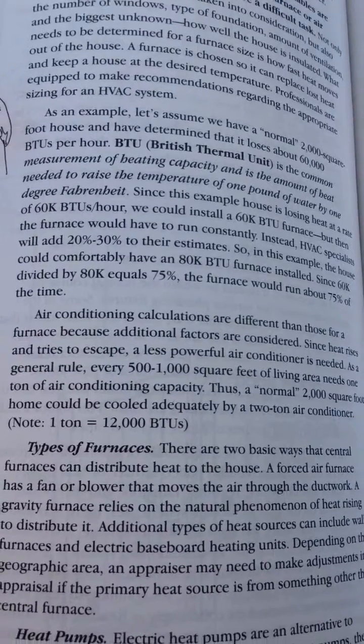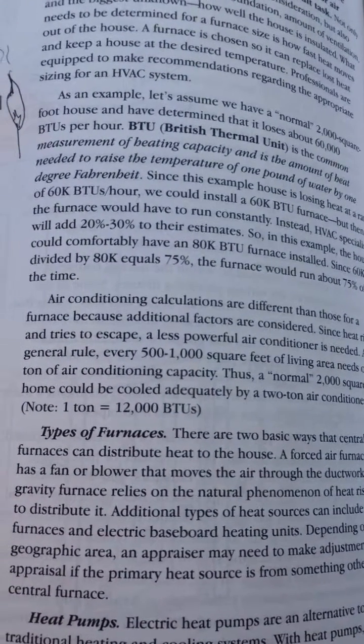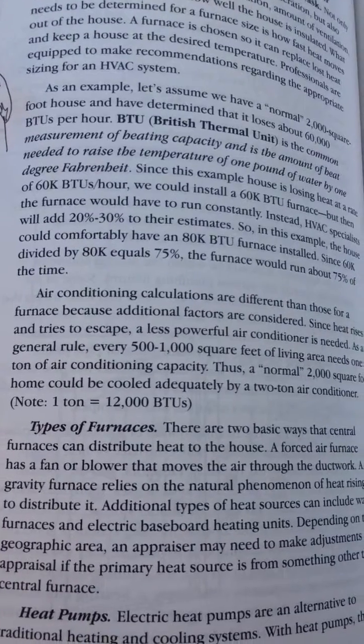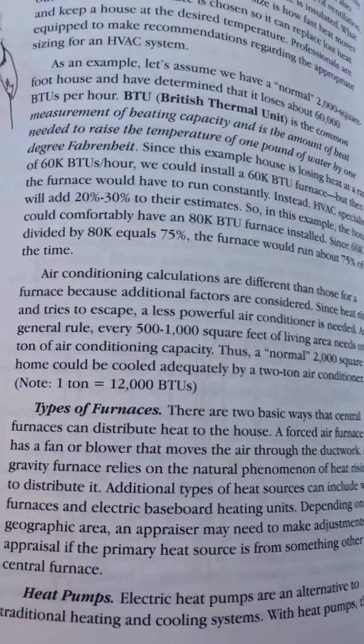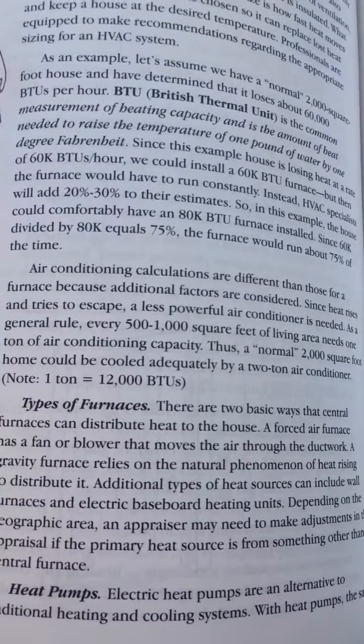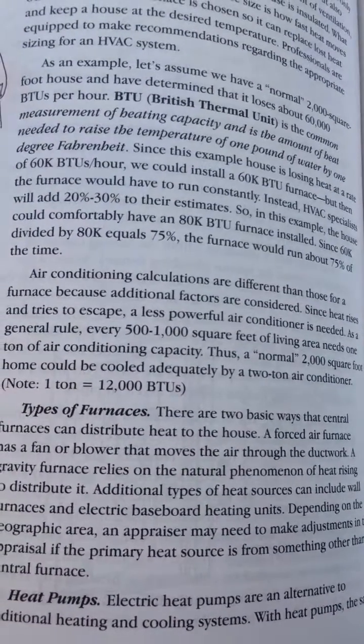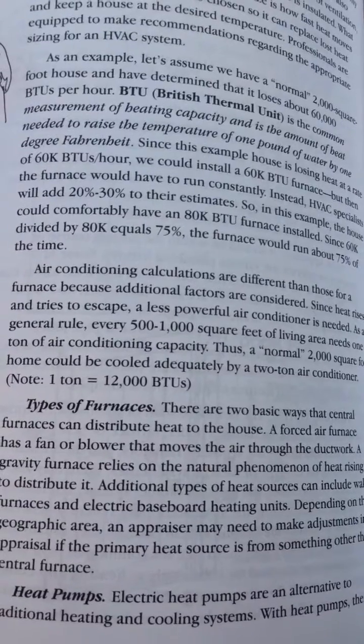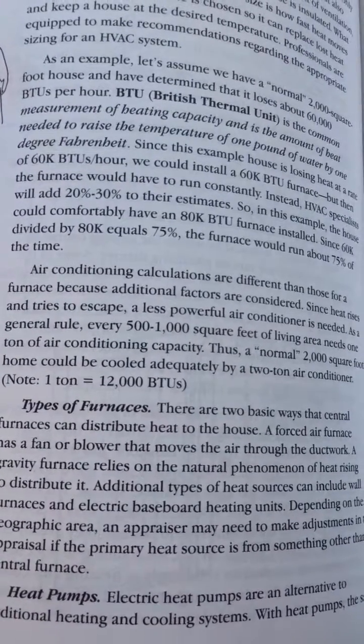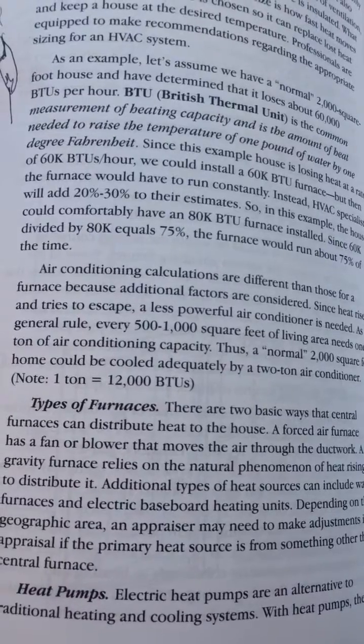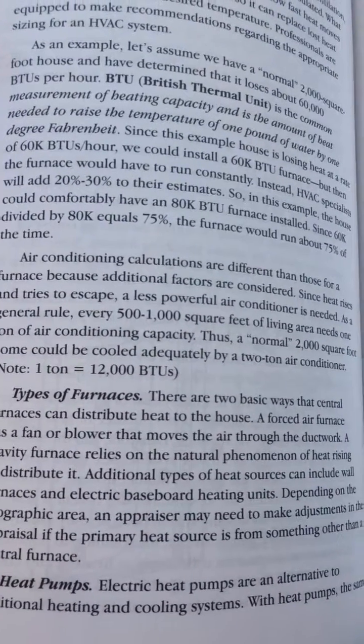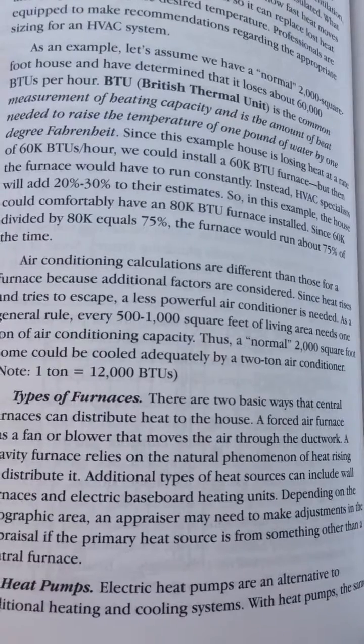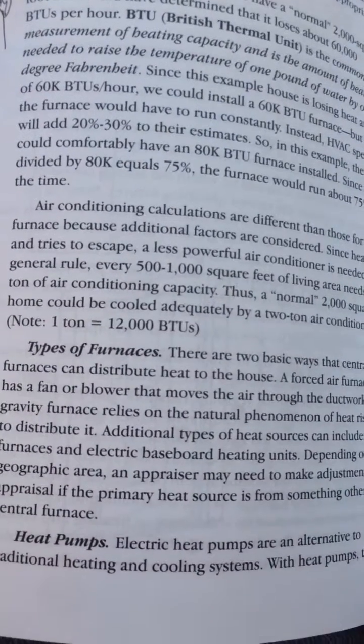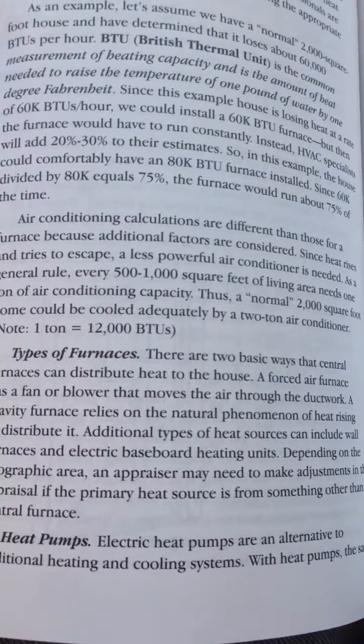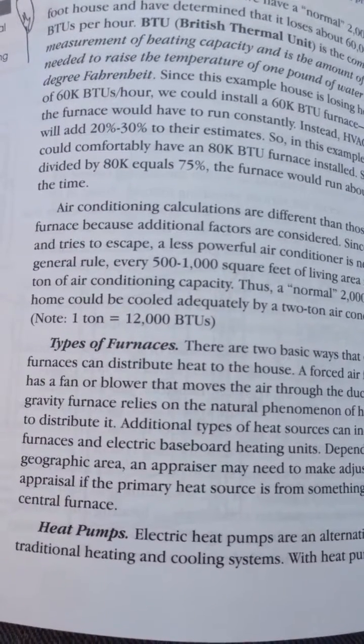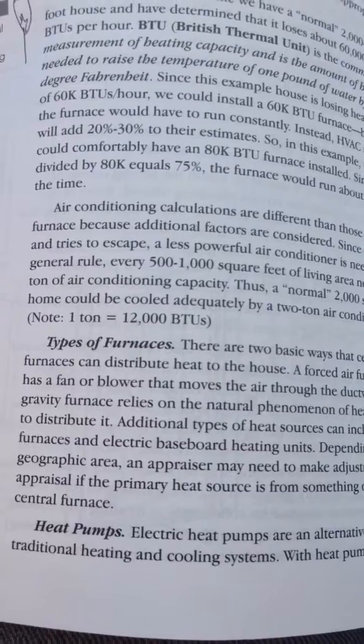Air conditioning calculations are different than those for a furnace because additional factors are considered. Since heat rises and tries to escape, a less powerful air conditioner is needed. As a general rule, every 500 to 1,000 square feet of living area needs 1 ton of air conditioning capacity. Thus, a normal 2,000 square foot home could be cooled adequately by a 2-ton air conditioner. Note, 1 ton equals 12,000 BTUs.